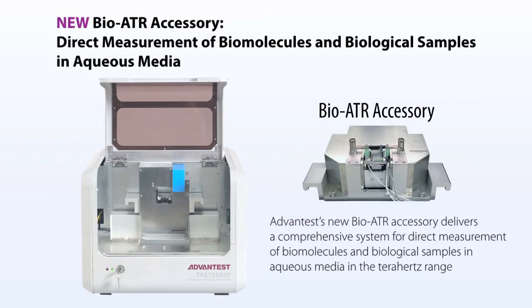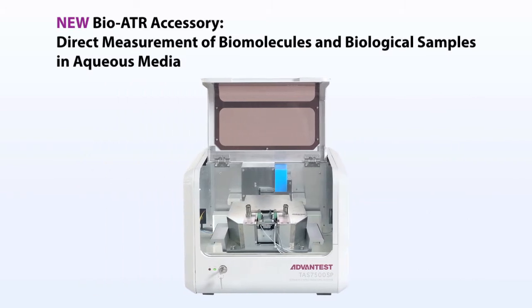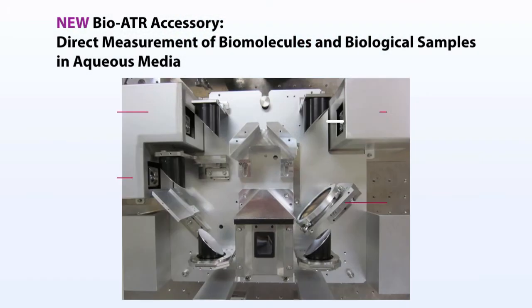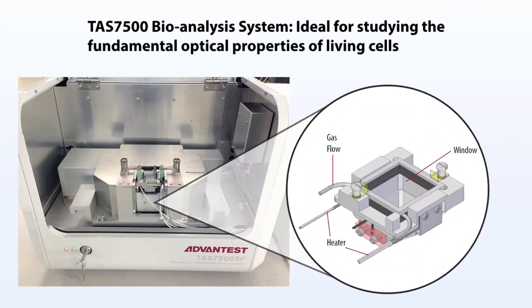Advantest's new bio ATR accessory delivers a comprehensive system for direct measurement of biomolecules and biological samples in aqueous media in the terahertz range. It allows for attenuated total reflectance, or ATR, measurements to be made in an environmentally controlled sample chamber. Its highly stable dual beam optical design compensates for long-term terahertz signal fluctuation, allowing for time series measurements to be made over longer intervals. The bio ATR accessory provides independent temperature control of the ATR crystal and the sample chamber, a convenient gas flow inlet, and a transparent window on the sample chamber to allow for microscopic observation.